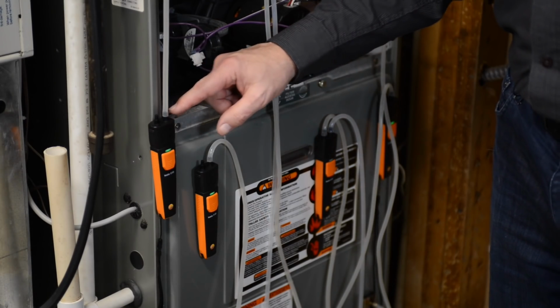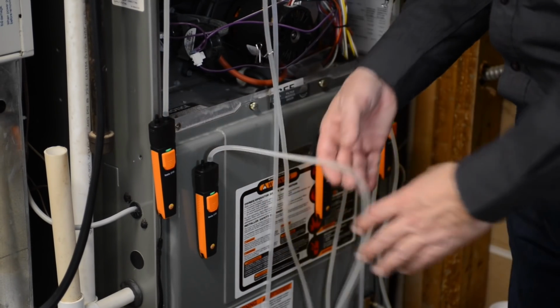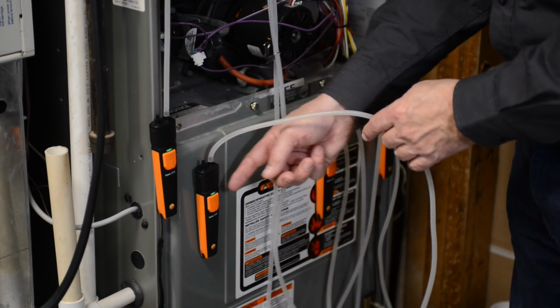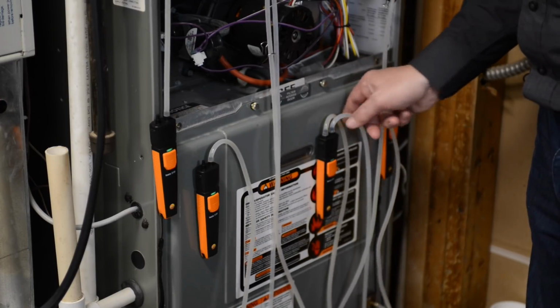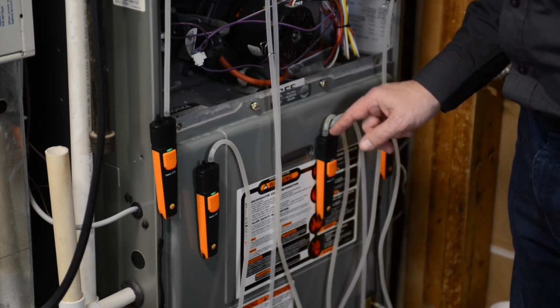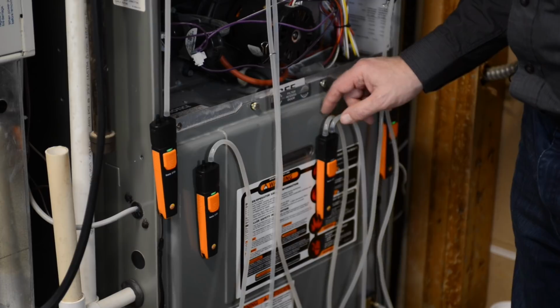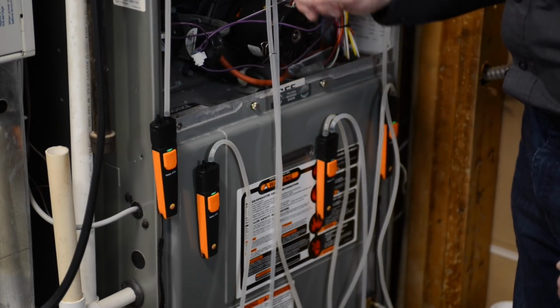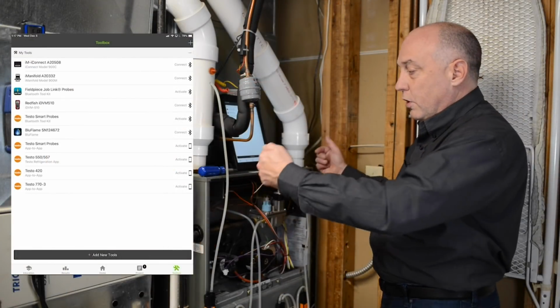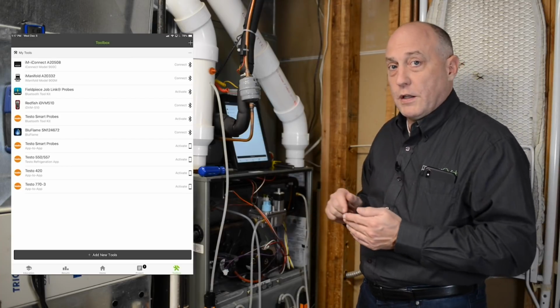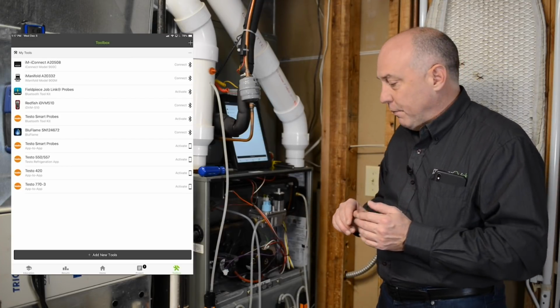So you can see I've got my vent pressure going up to my vent right here. I've got my incoming gas pressure right here. I've got my manifold pressure right here, and then I'm measuring total external static. I have a pressure tip down here at the bottom of the furnace. I have another one inside the furnace back here because I can't drill on either side to get in, so I had to go through the front of the furnace for the static pressure tip.